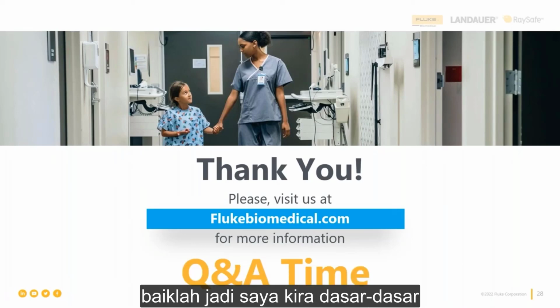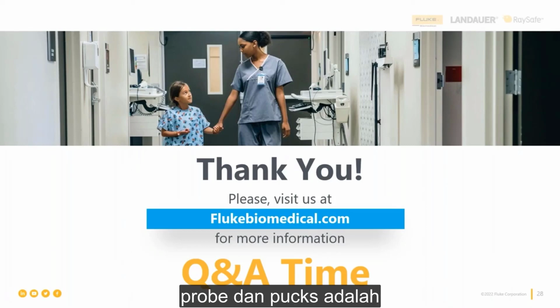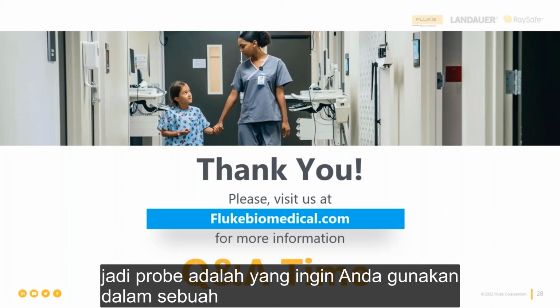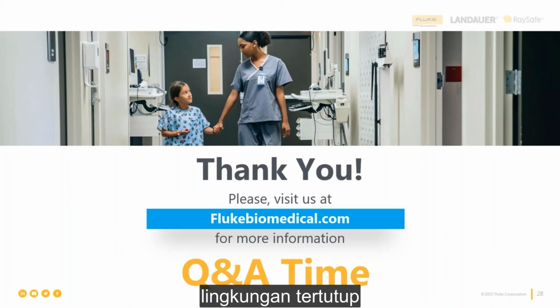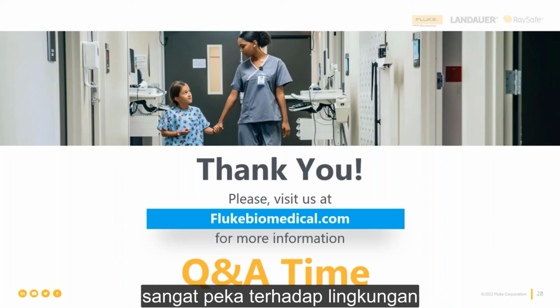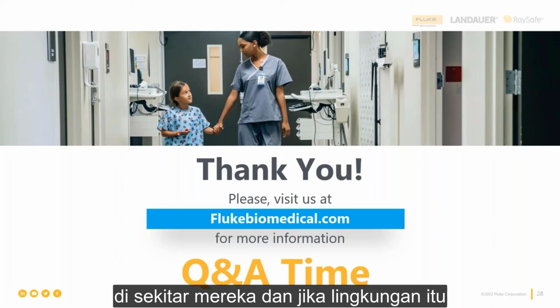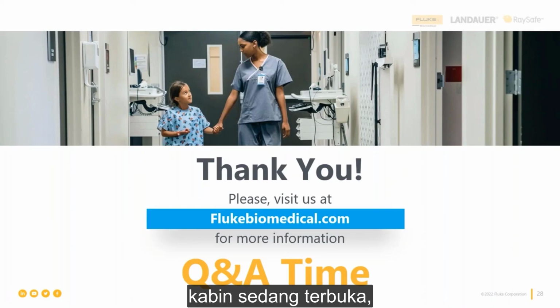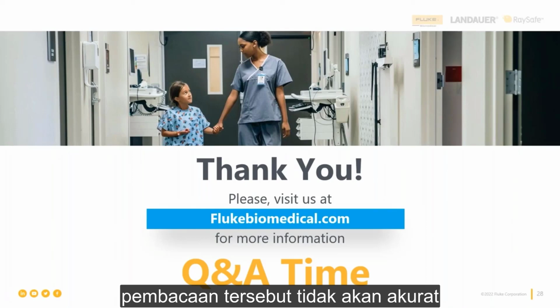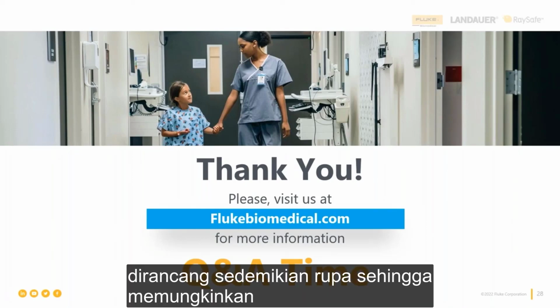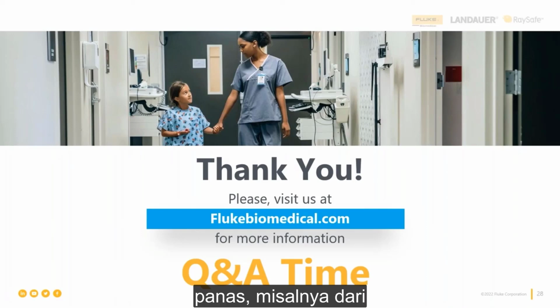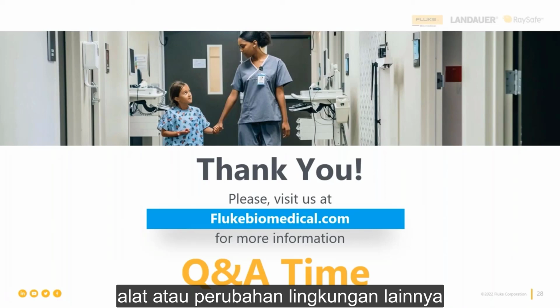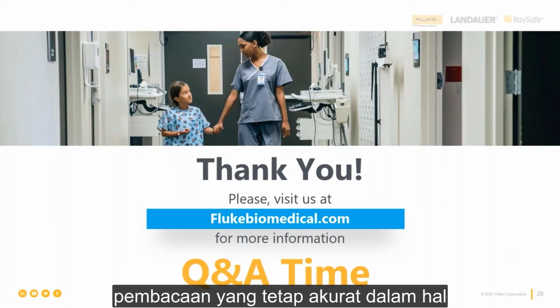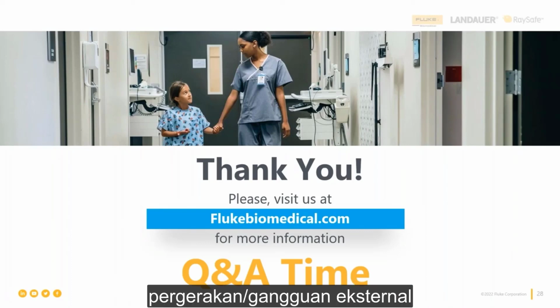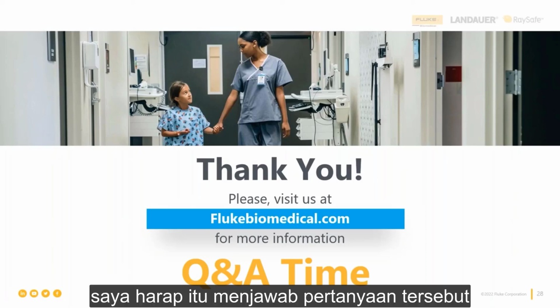All right, the basic difference between the probes and the pucks is the environment they're being used in. Probes you want to use in an enclosed environment, for example a transport incubator, because the probes are very sensitive to the environment around them. If that environment is affected by something, say the incubator cabin is open, those readings will not be accurate. At the same time, the pucks are designed to absorb heat from the device or other environment changes, and that is why they still provide accurate readings even with external air movement or something like that. I hope that answers the question.